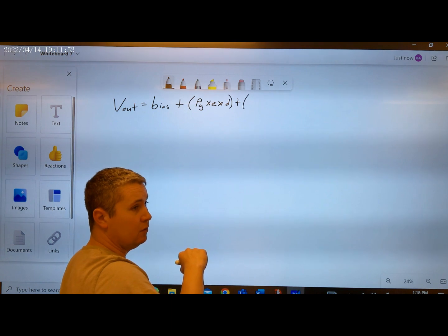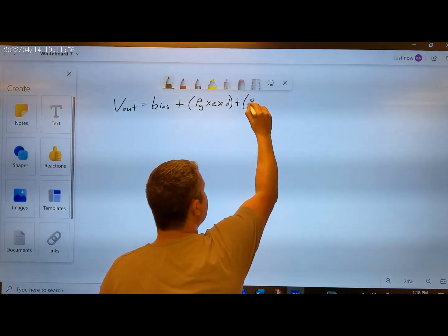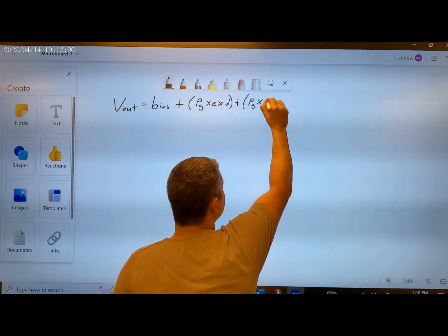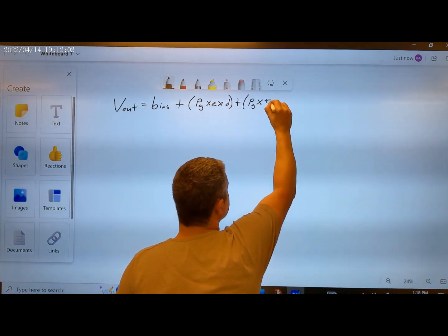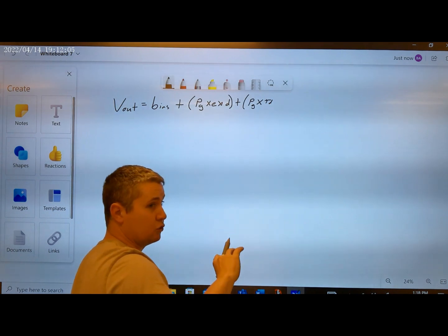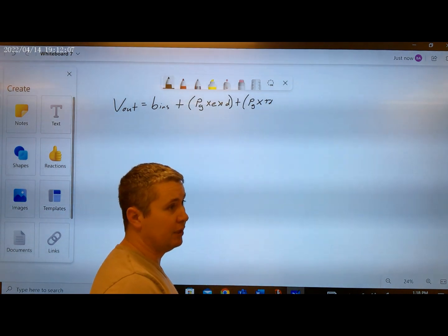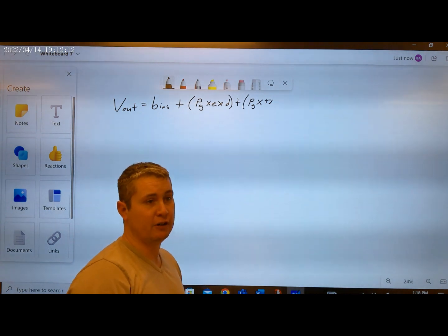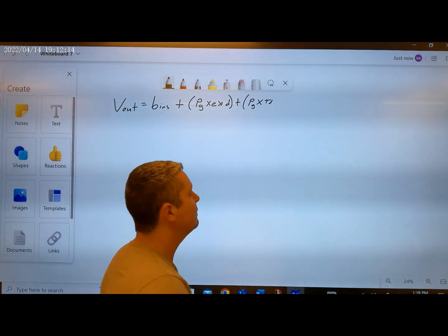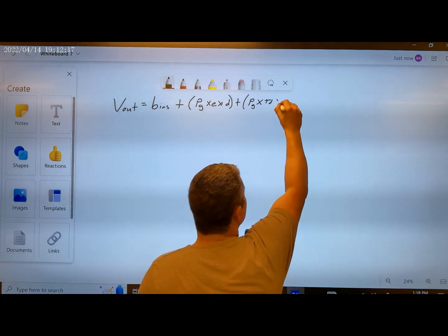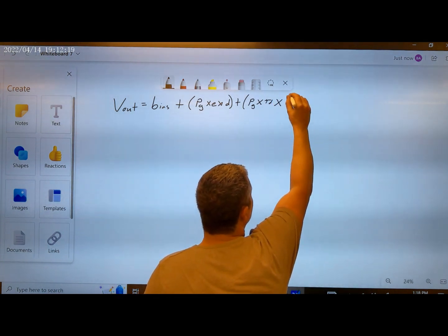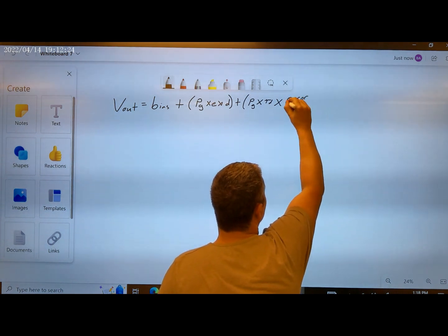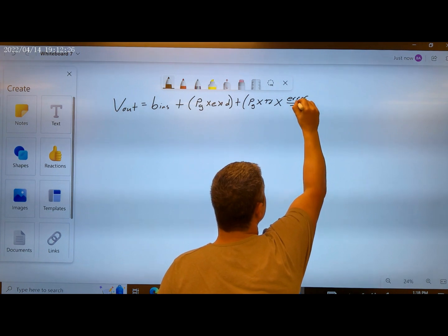We are going to go proportional gain times your derivative gain. In our case, it's TD on our controllers, okay? But in a lot of other places you'll see it, it'll be DG for derivative gain, times your error over time.